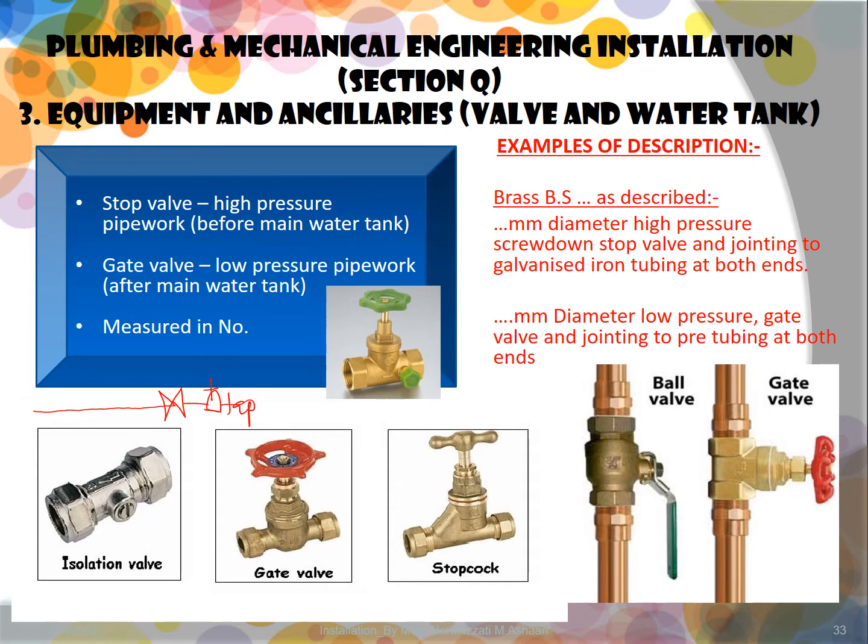Even though we can see nowadays in one room or in one bathroom, sometimes you only have one or two stop valves, even though there are 5 outlets. So that is a different story if they are different. But principally, every single outlet of the sanitary fitting has to be installed with a valve. Why? Because we would like to control the flow of the water in case you would like to change the water tap, in case you would like to clear all the blockage and so on.